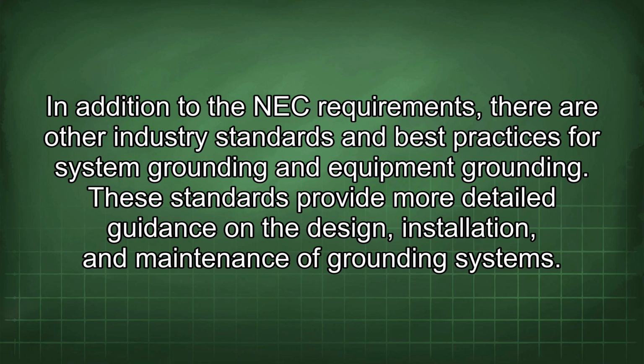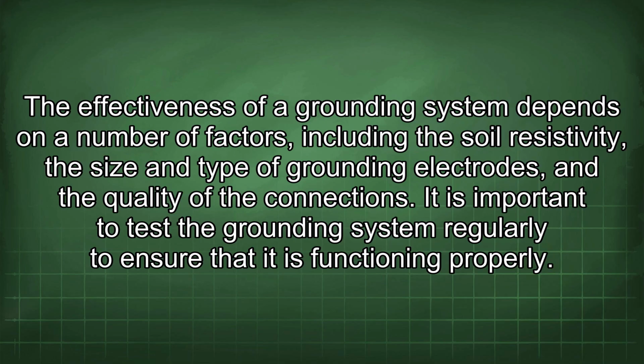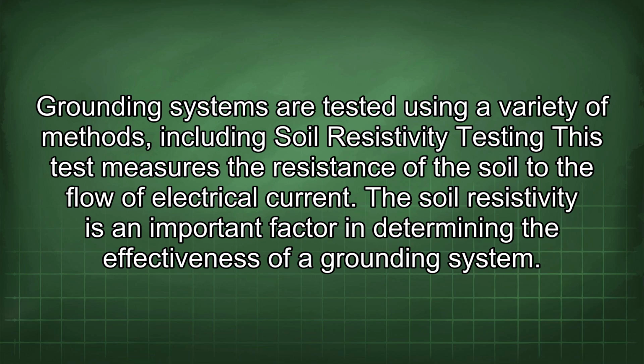In addition to the NEC requirements, there are other industry standards and best practices for system grounding and equipment grounding. These standards provide more detailed guidance on the design, installation, and maintenance of grounding systems. The effectiveness of a grounding system depends on a number of factors, including the soil resistivity, the size and type of grounding electrodes, and the quality of the connections. It is important to test the grounding system regularly to ensure that it is functioning properly. Grounding systems are tested using a variety of methods, including soil resistivity testing. This test measures the resistance of the soil to the flow of electrical current. The soil resistivity is an important factor in determining the effectiveness of a grounding system.